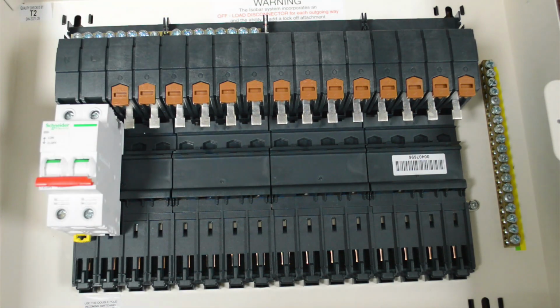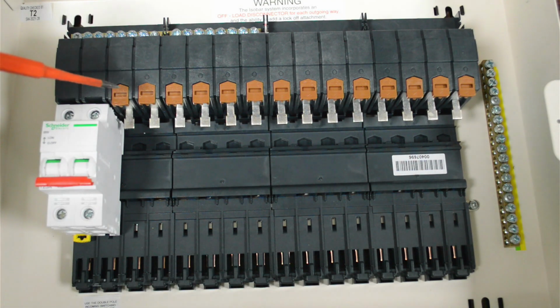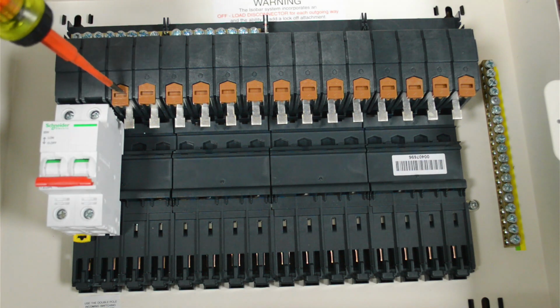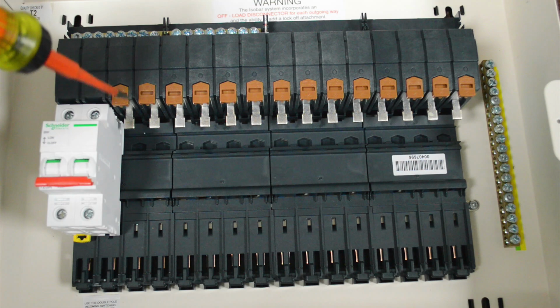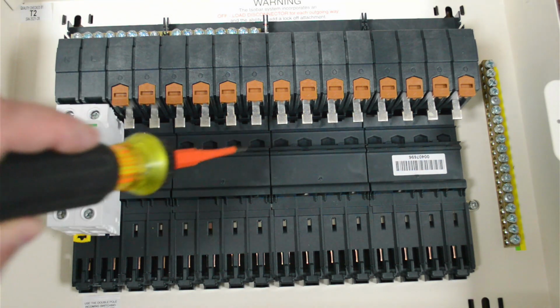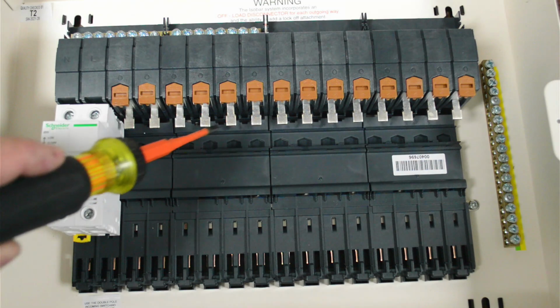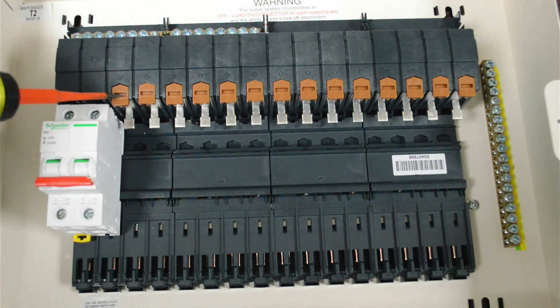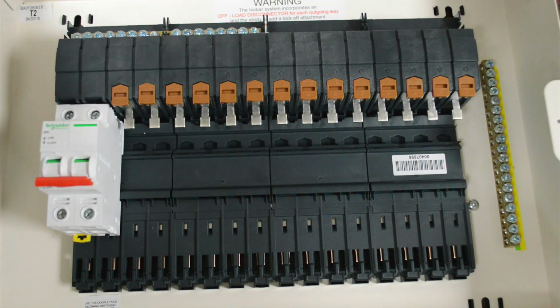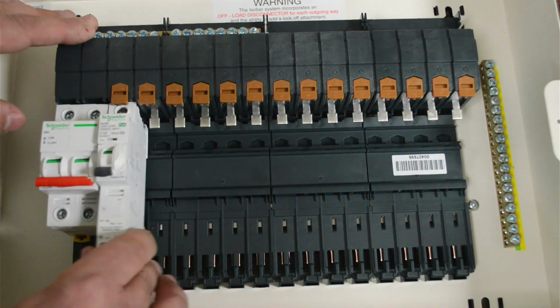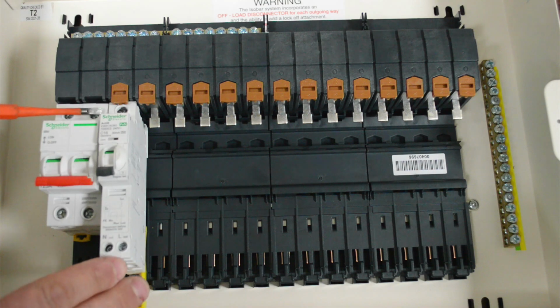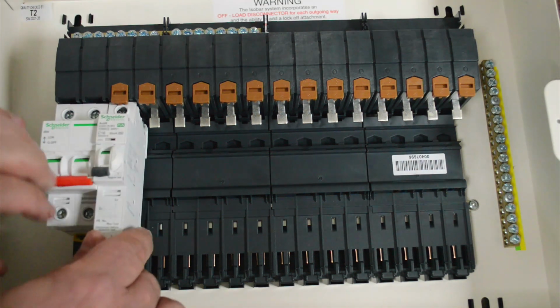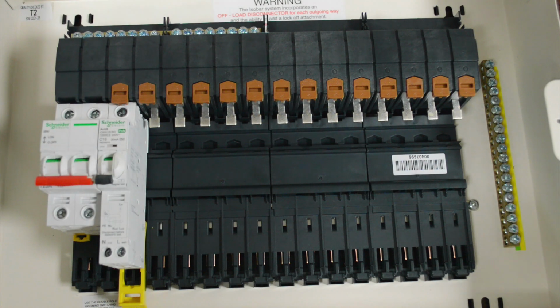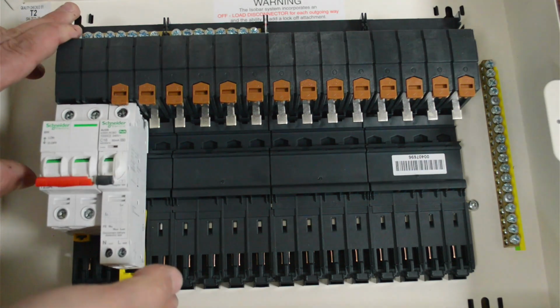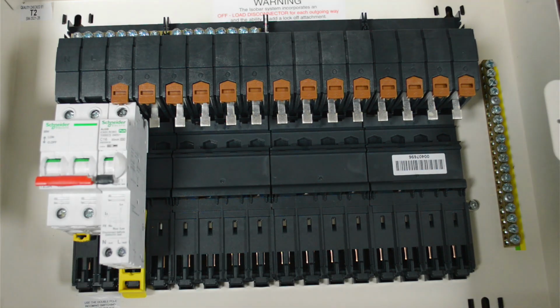Now these boards are quite safe, or as safe as you can perhaps expect them to be. So when there is no RCBO or MCB connected, these actually do isolate. So even if this is in the on position, these will not be energized because of this tab here. So if I demonstrate this being installed, if I can actually do it on camera, you see that locks under the brown tab there, so it's pushed underneath it, and then you simply clip it down, and that's it, locked in.